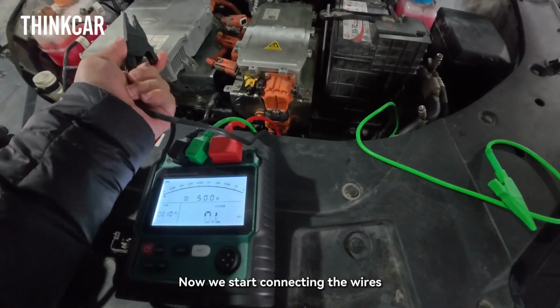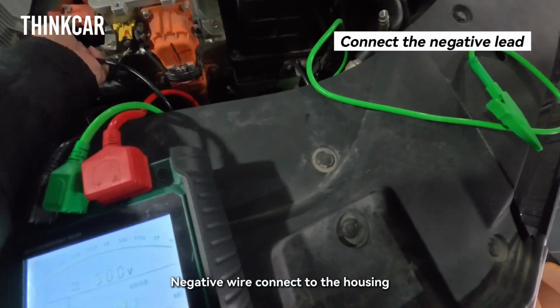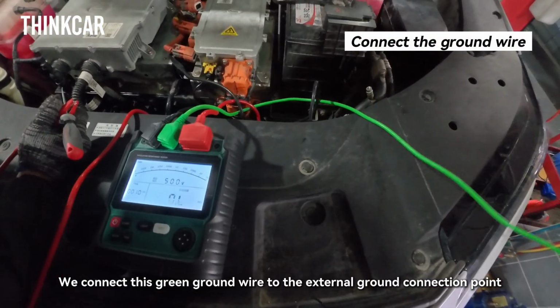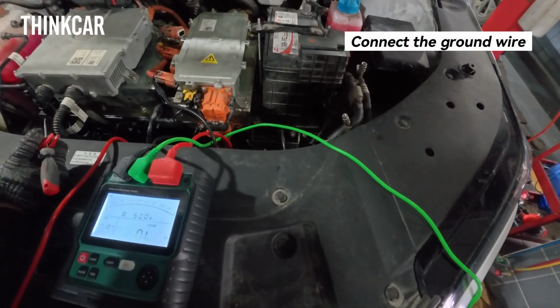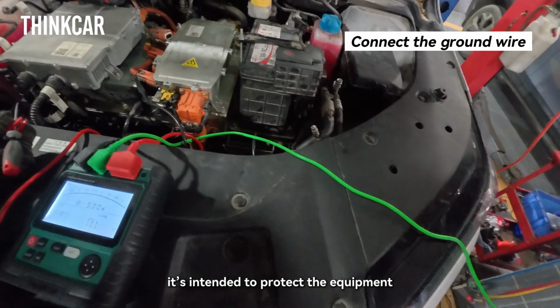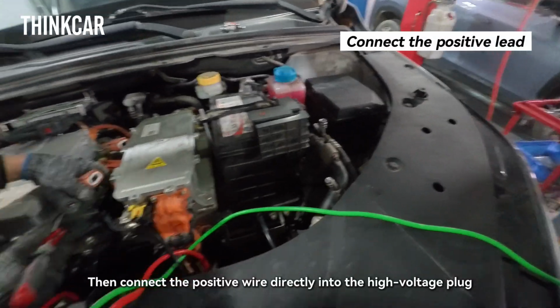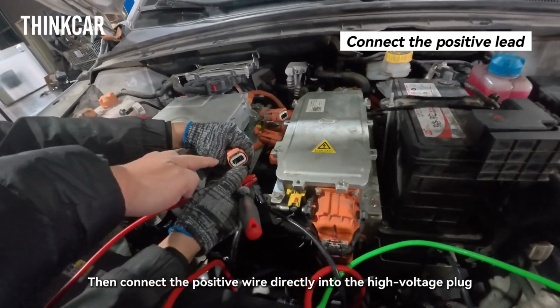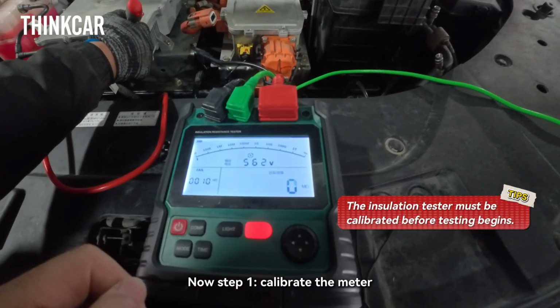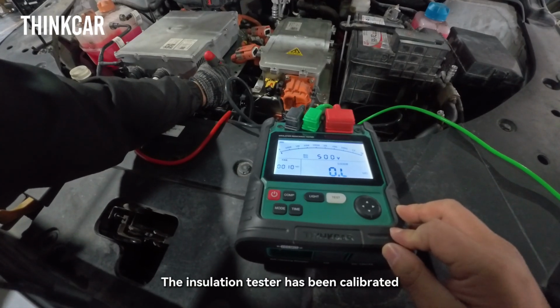Now we start connecting the wires. Negative wire connect to the housing. We connect this green ground wire to the external ground connection point. Though it's not required, it's intended to protect the equipment. Then connect the positive wire directly into the high voltage plug. Now step 1. Calibrate the meter. The insulation tester has been calibrated.